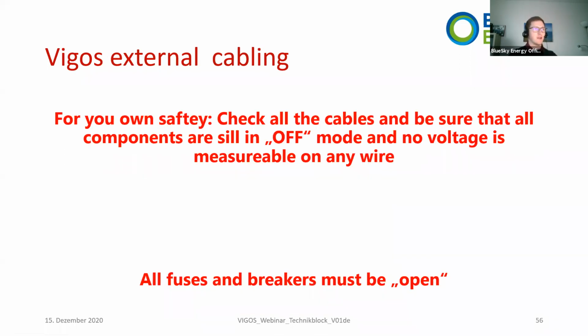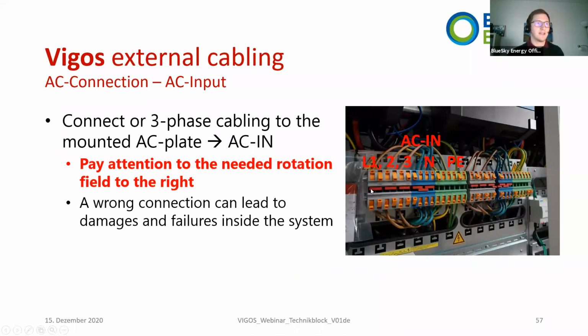If you do external cabling, please always check the cables and be sure that all components are still switched off and no voltage is measurable on any wire. Please always make sure of that before connecting anything. So the AC input looks like that. This is the connection point for you, where you can add the 3-phase system. Please always pay attention to the needed rotation field to the right. That means the phase sequence needs to be L1, L2, L3 in this direction, and let me show it to you in the correct way inside the camera. The phase needs to spin to the right. Hope that is understandable. And here you have the connection points for L1, L2, L3, here for the neutral wire, and here for the ground wire or earth wire.